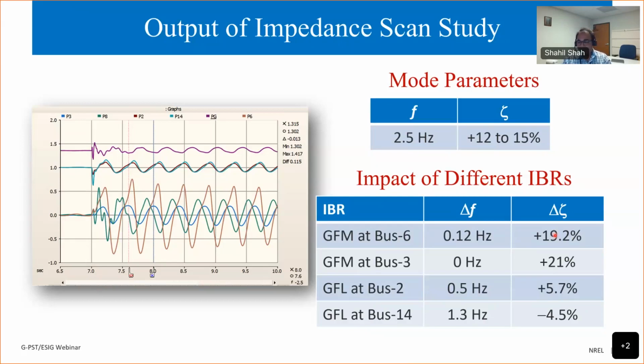stable operation. And here I would like to add a disclaimer that whatever I'm talking about here is all small signal stability. So let's say the small signal stability analysis using impedance scan tools tells you that you need X amount of grid forming capacity in the system. That might be different from the transient stability standpoint, which is for frequency stability or voltage stability. So everything that I'm talking about here is small signal stability, or control interactions and oscillations. That's a separate part.